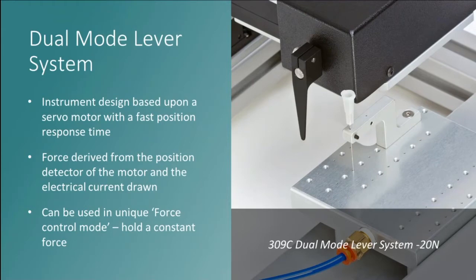So this is what we would call a closed loop system, as opposed to an open loop system, which does not provide feedback. We use this functionality in combination with the electrical current drawn by the motor, since it's proportional to the load seen by the instrument. This provides, I think, a very elegant means of obtaining the instantaneous tensile force.